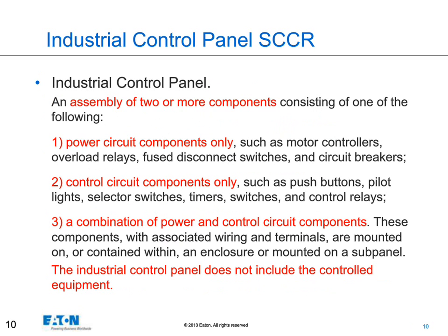An industrial control panel is a general term that identifies an assembly with two or more components in a box. Those components might be power circuit components, control components, or more likely a combination of both power and control. It's important to note that an industrial control panel does not include the controlled equipment — if it did, it would then be considered industrial machinery.